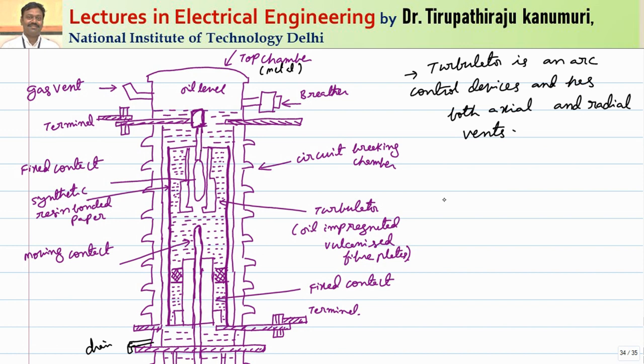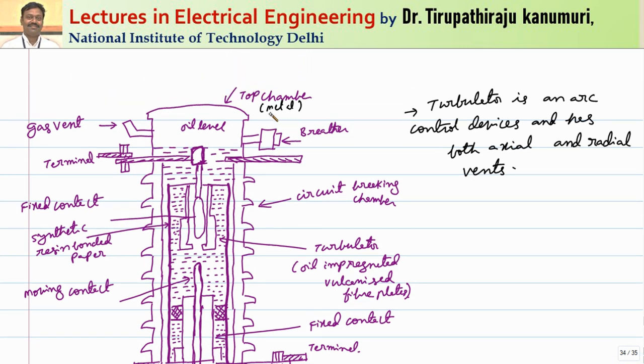Coming to the construction of the circuit breaker, it basically contains three chambers. The first is the top chamber, made of metal, which contains a gas vent and a breather so that whenever high pressure gas is produced, it can easily escape through the gas vent. This top chamber is connected to the circuit breaking chamber. The circuit breaking chamber is made of porcelain on the outer side, and inside the porcelain, one more cylinder of synthetic resin bonded paper is provided to give extra insulation.